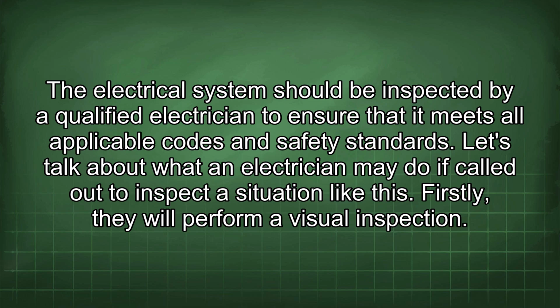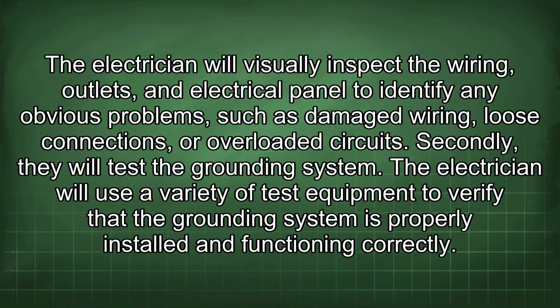Firstly, they will perform a visual inspection. The electrician will visually inspect the wiring, outlets, and electrical panel to identify any obvious problems such as damaged wiring, loose connections, or overloaded circuits. Secondly, they will test the grounding system. The electrician will use a variety of test equipment to verify that the grounding system is properly installed and functioning correctly.